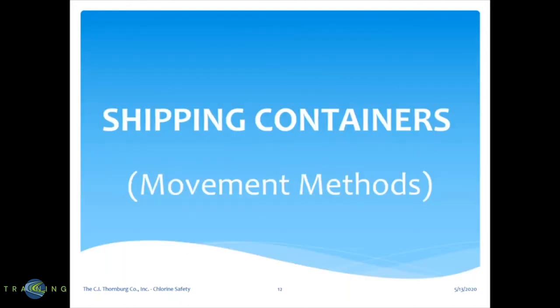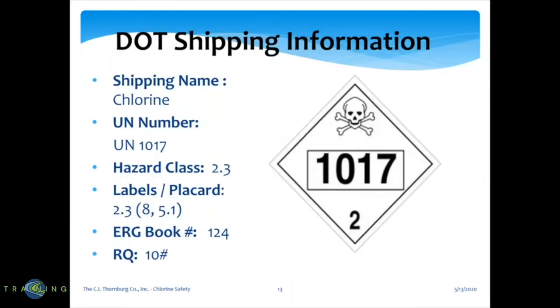Shipping containers and movement methods. DOT shipping information: when you see us pull up onto your property with chlorine cylinders, you'll see the placard 1017, class 2. The shipping name is chlorine. UN number is 1017. Hazard class is 2.3, which will be noted on labels and the placard. In the emergency response guidebook, which all drivers have, chlorine is on page 124.